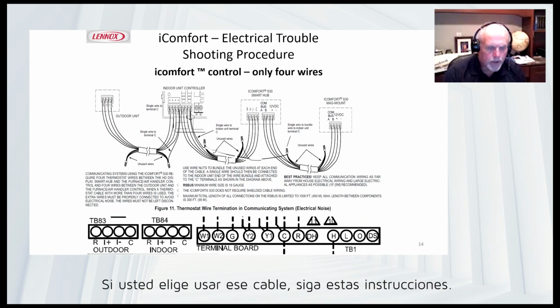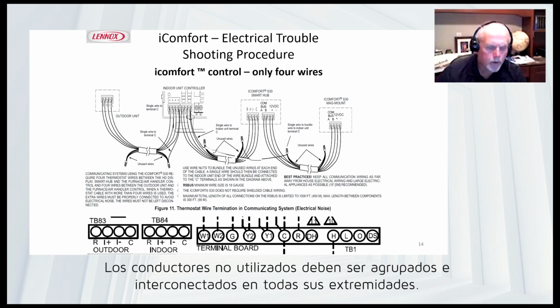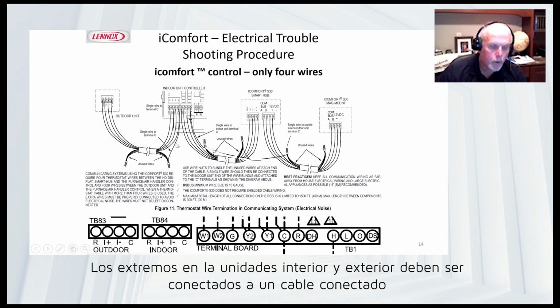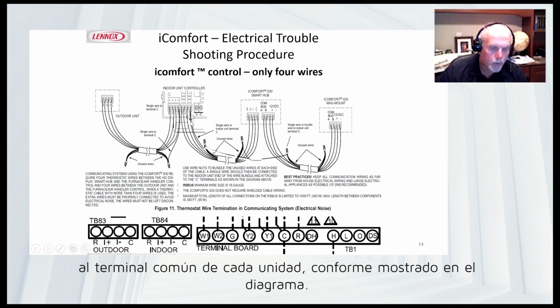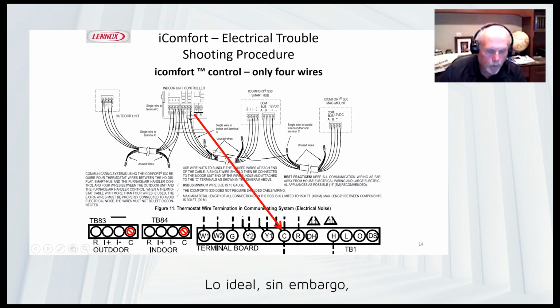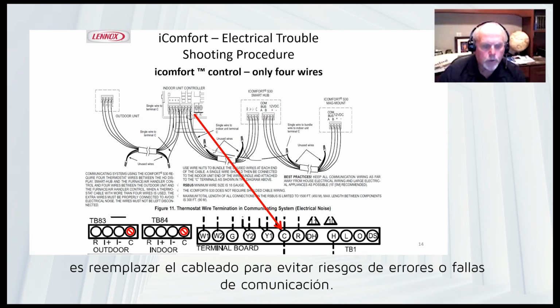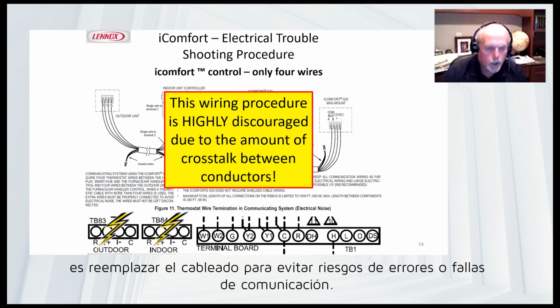If you choose to use that, this is how we want you to do it. Okay. So any unused conductors, putting under a wire nut and draining those back to common at the indoor board. Okay. So wire nut here with a wire going up to common, and the same for any other unused conductors, and bringing those all the way back to common at the indoor board. However, we do not recommend this way. If you can change the wiring, it is better to do so to cut down on communication errors. Okay. So if you choose to do it this way, there are ways to wire that to help cut down on communication errors. But if you can change the wire to two conductor cables, that would be better.